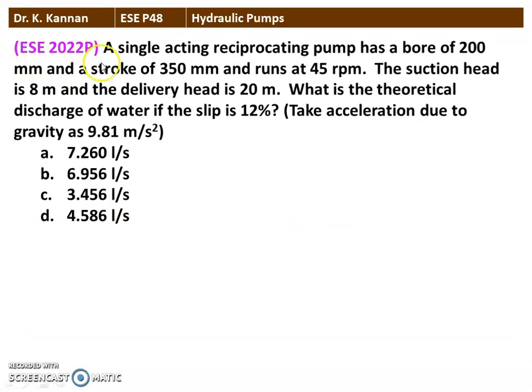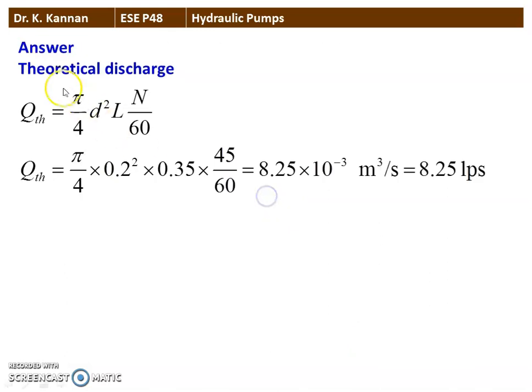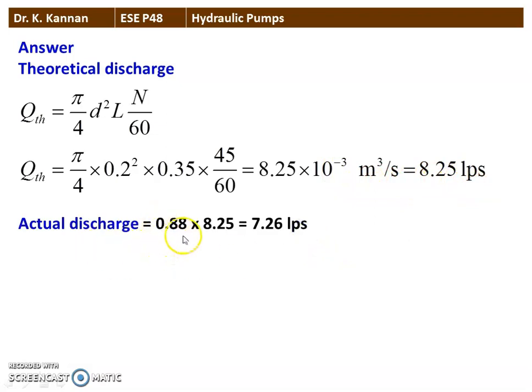The next question from the 2022 question paper: A single acting reciprocating pump has a bore of 200 millimeter, stroke of 350 millimeter, and runs at 45 RPM. The suction head is 8 meter and the delivery head is 20 meter. What is the theoretical discharge of water if the slip is 12%? Take g = 9.81 m/s². The theoretical discharge = (pi/4) × 0.2² × 0.35 × 45/60 = 8.25 × 10⁻³ cubic meters per second = 8.25 liters per second. Actual discharge = 0.88 × theoretical discharge = 7.26 liters per second. The correct answer is 7.260 liters per second.